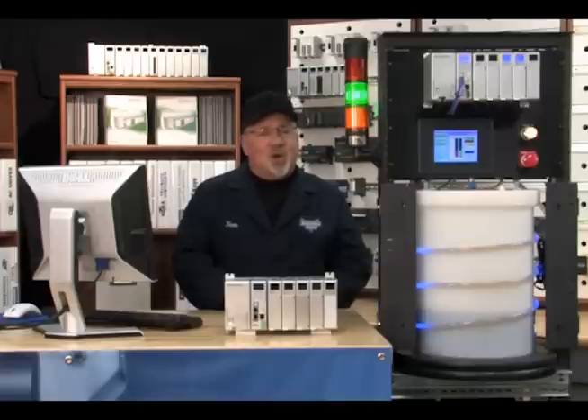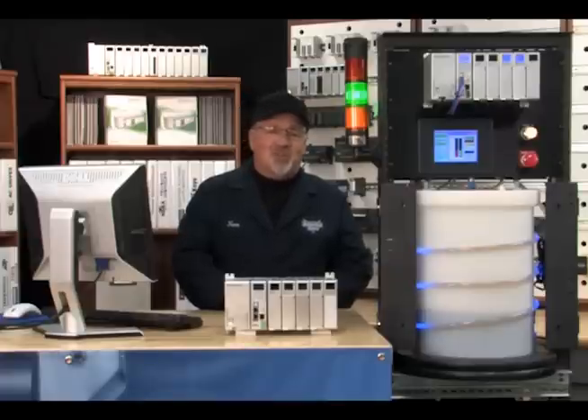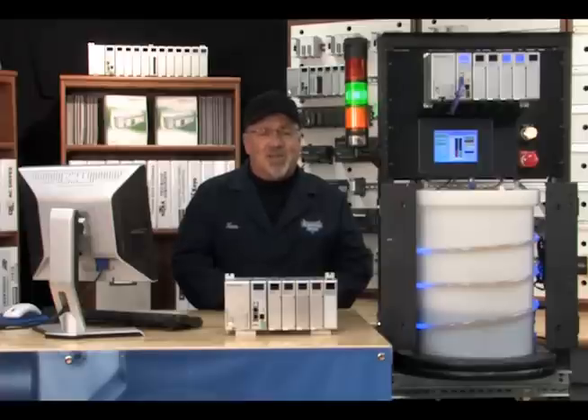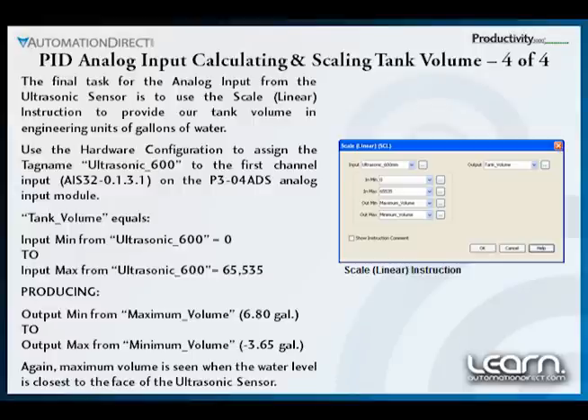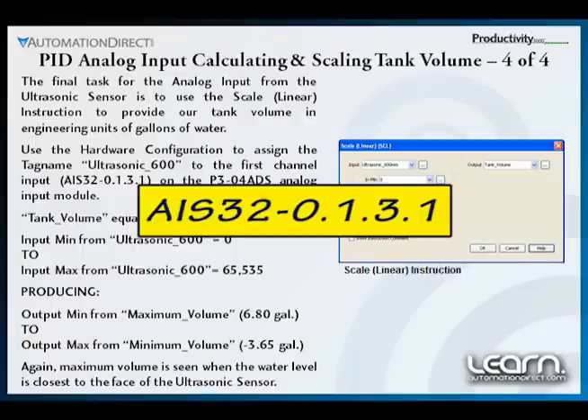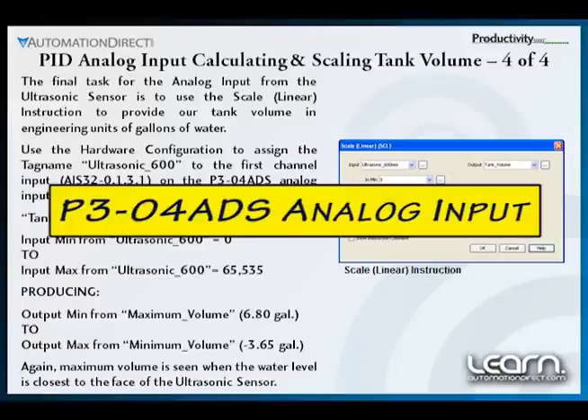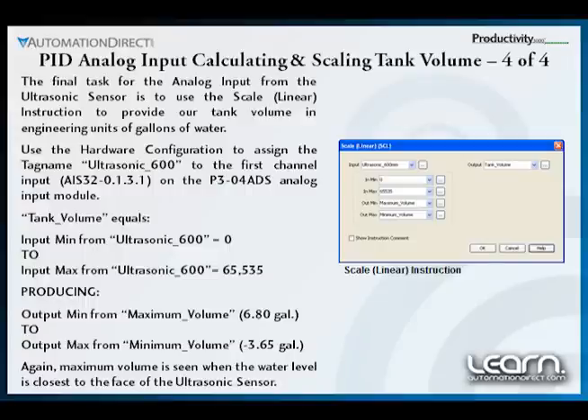Now that we have a better understanding of what is going on with the analog input module that is fed with the 0 to 10 volt DC analog signal from the ultrasonic sensor, we are ready to use the scale linear instruction to provide our tank volume in engineering units of gallons of water. But first we need to assign a tag name to the first channel AIS32-0.1.3.1 on our P3-04ADS analog input module to which we have our ultrasonic sensor wired. We will rename this existing tag name to ultrasonic_600, which represents the sensor's 0 to 10 volt DC analog signal with a maximum sense range of 600 millimeters.